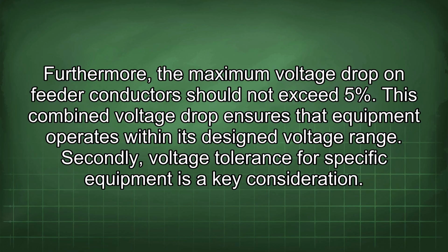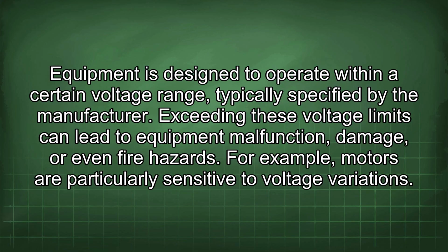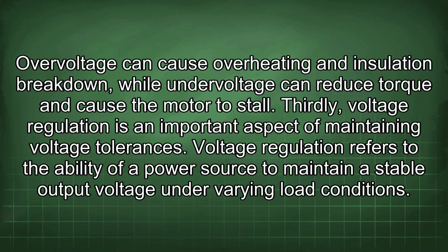Secondly, voltage tolerance for specific equipment is a key consideration. Equipment is designed to operate within a certain voltage range typically specified by the manufacturer. Exceeding these voltage limits can lead to equipment malfunction, damage, or even fire hazards. For example, motors are particularly sensitive to voltage variations. Overvoltage can cause overheating and insulation breakdown, while undervoltage can reduce torque and cause the motor to stall.